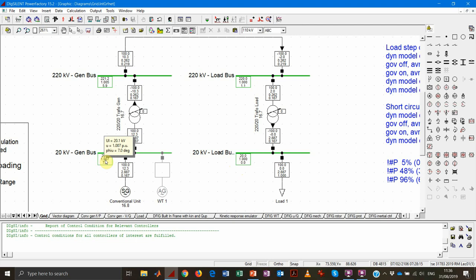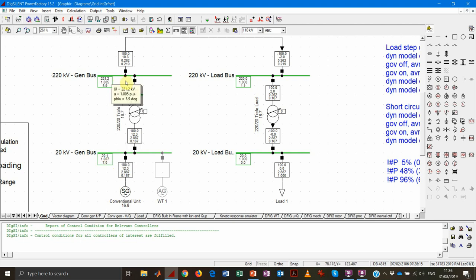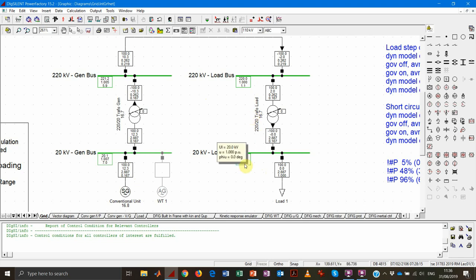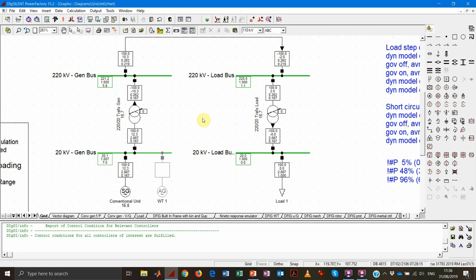The generator will be the one providing the 12.3 MVAr necessary. Since we set the voltage at the load bus to one per unit, the generator bus voltage has to be slightly higher to allow reactive power to flow through the system and magnetize the different components. Also, the generator bus voltage has an angle that leads the rest of the system, because active power is flowing and requires displacement of the voltage phasors. The angle goes from 0 degrees to 1.1, 5.9, 7 degrees — depending on the reactance values, with the largest contribution coming from the line.